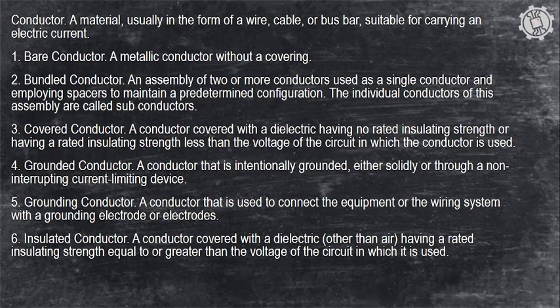So kaya, if nakalagay is that wire is good only for 2,000 volts, dapat the application must be up to 2,000 volts. For high voltage naman, it depends on the system voltage of the insulation. If that is a 69 kV, iba din yung insulation strength niya. Hindi pwede na kunyari 69 kV tapos ang gagamitin mo is 2,000 volts din. Dapat mas mataas pa yung dielectric strength. So that is to prevent our insulation or the covering of our conductor from burning or being damaged. Kasi kapag nawala na yung ating insulation, our conductor is now bare, which is subject to short circuit or accidental contact.